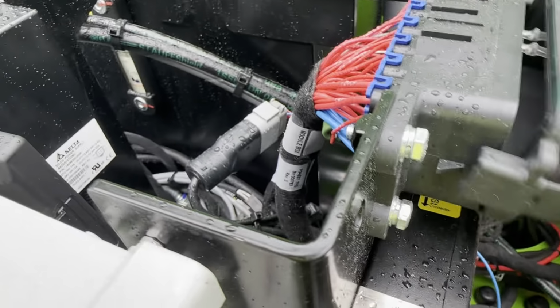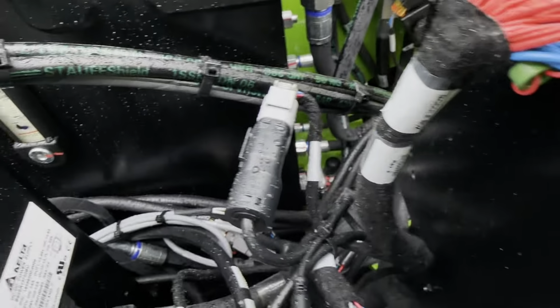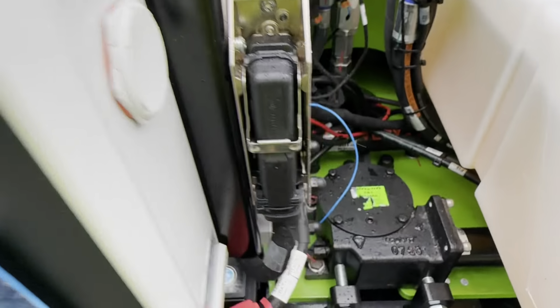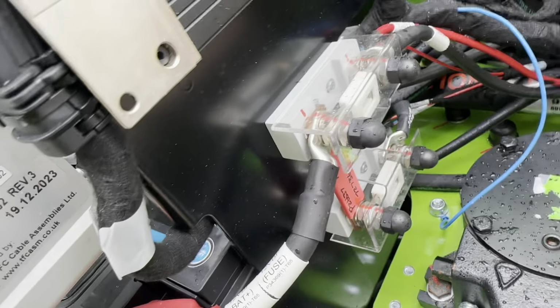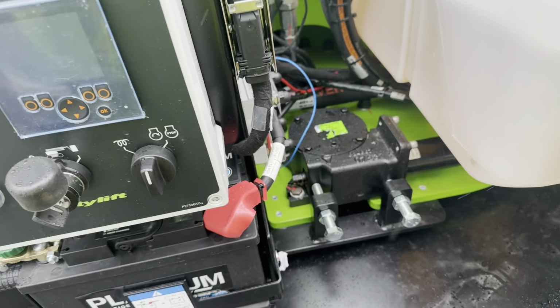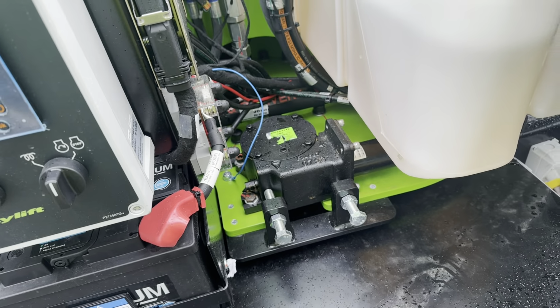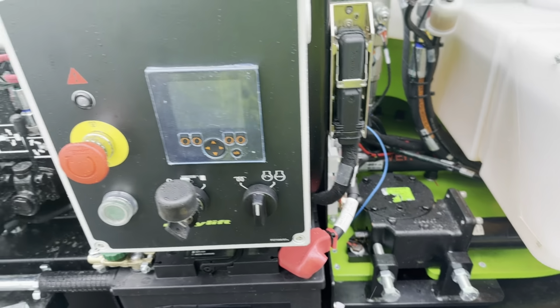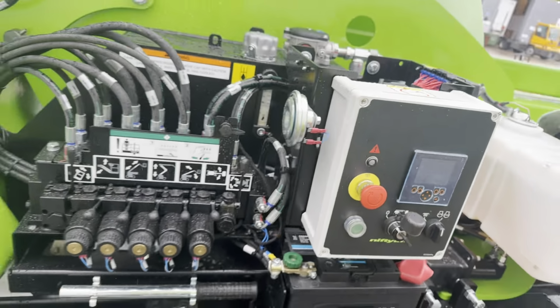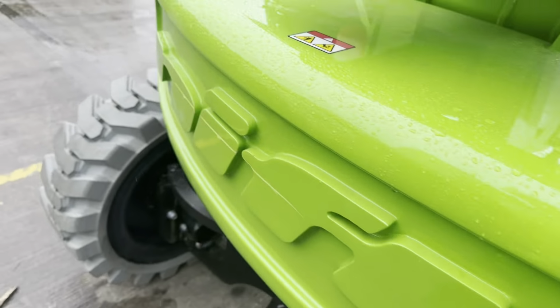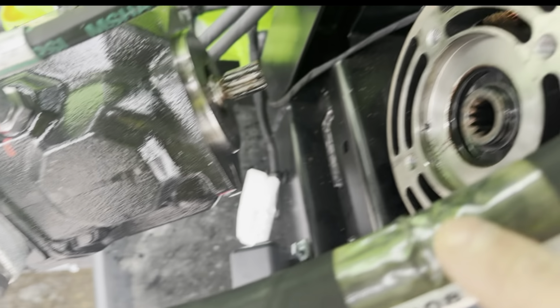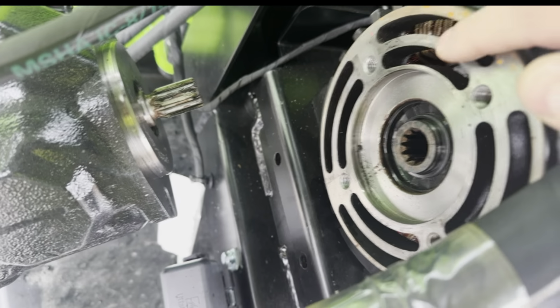The one on the controller failed. That could lead to a failing controller if it was a shutdown through the CAN bus. If the CAN bus errors happen, then maybe the system just shut down. If the controller was under load, then maybe it could result in a blown phase. I want to remove the pump just to see if there's nothing wrong inside the motor.